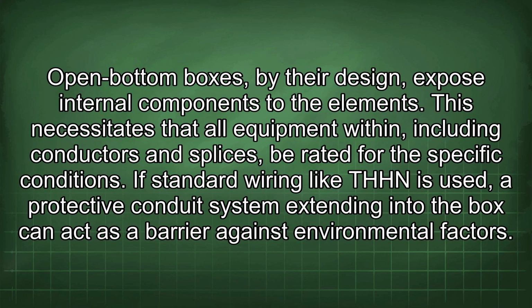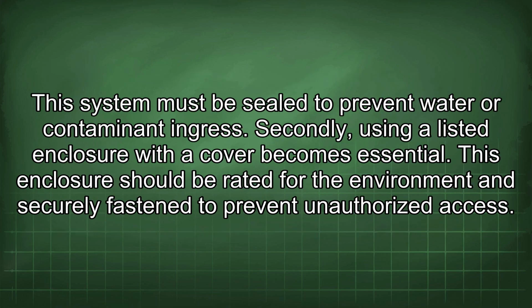Open-bottom boxes, by their design, expose internal components to the elements. This necessitates that all equipment within, including conductors and splices, be rated for the specific conditions. If standard wiring like THHN is used, a protective conduit system extending into the box can act as a barrier against environmental factors. This system must be sealed to prevent water or contaminant ingress.